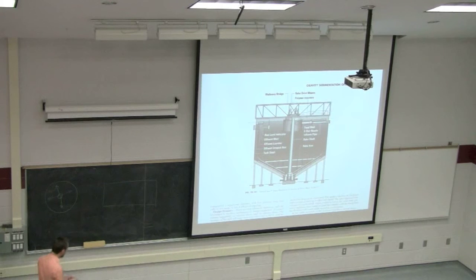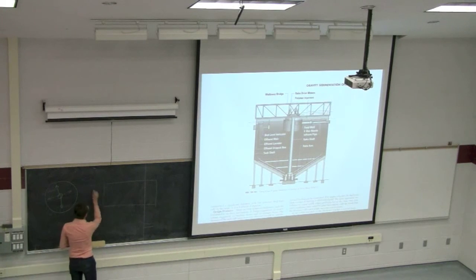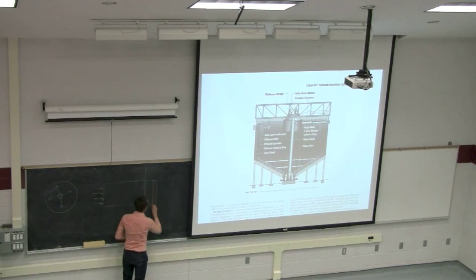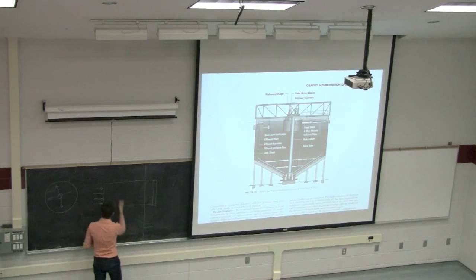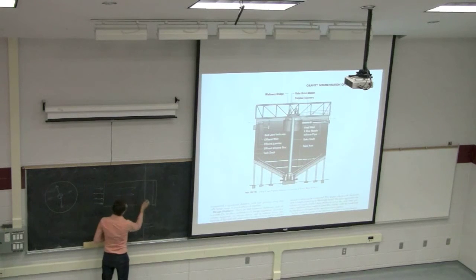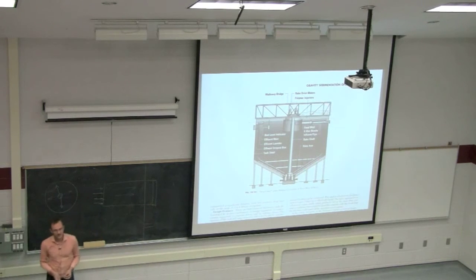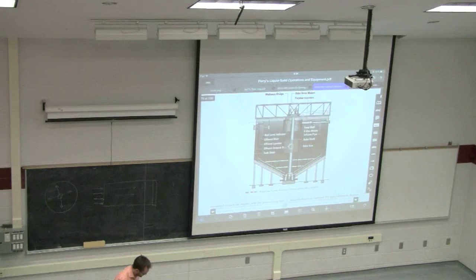In a rectangular tank, you would pick one side as your feed. So the material is fed evenly, distributed at that one edge. And then your overflow launder and weir is over here on the other side. So the material is simply flowing across and the solids are settling down. We're only looking at the top view here, but the solids are settling downward and collecting at the bottom. And there's a conveyor belt to remove that as well. So that's the principle of operation of those units.